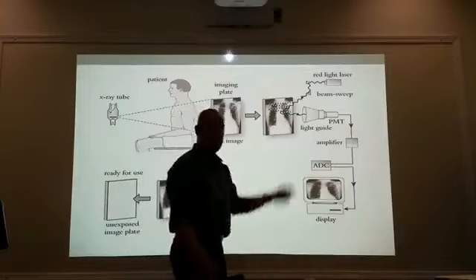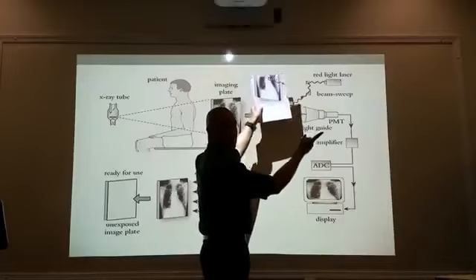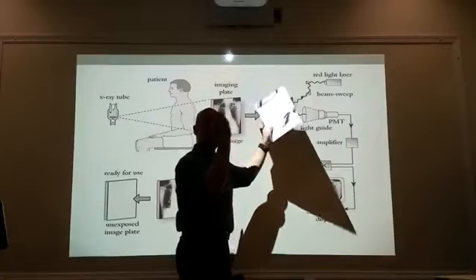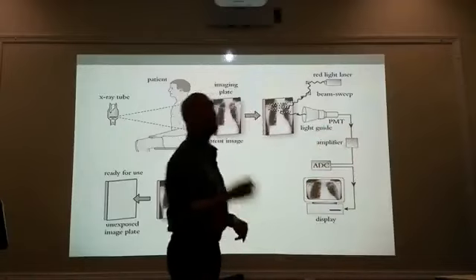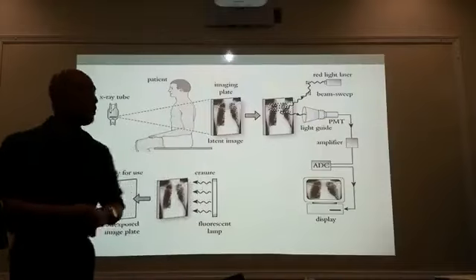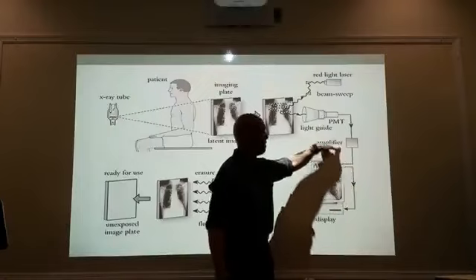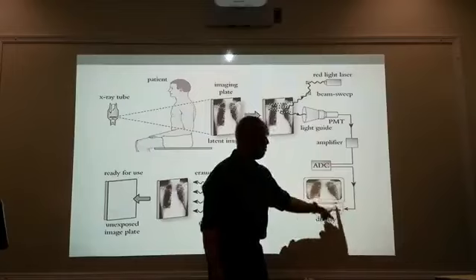You put your cassette in the image reader. The PSP is removed. Now it gets scanned by the red laser light. As it's being scanned, the crystals are going to emit a blue-violet light. That then goes into your photomultiplier tube, your PMT, to amplify the light signal. It then goes into an analog-to-digital converter, and simply, your image pops up on the screen.